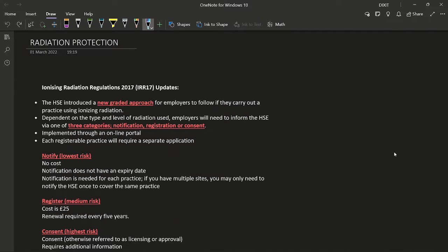For anyone who has already read the chapter, I'll briefly discuss recent updates. The Ionizing Radiation Regulations 99 (IRR 99) has been updated. The HSE has introduced a new graded approach for employers starting a new practice. Depending on the type and level of radiation used, employers will need to inform the HSE via one of three categories: notification, registration, or consent. Everything is done through an online portal and each registrable practice requires a separate application.